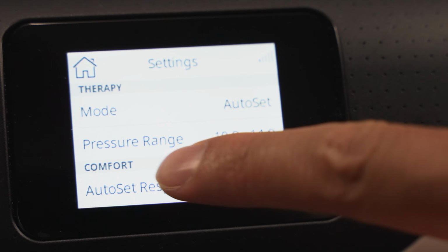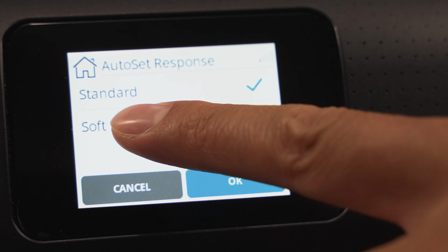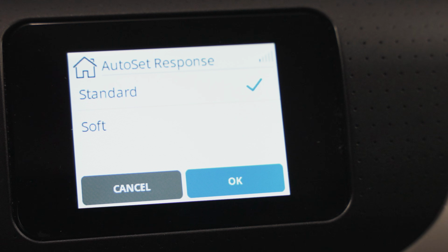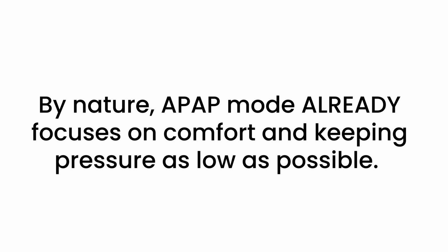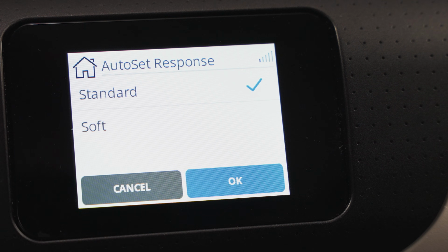Now let's go into comfort. So you're gonna see AutoSet response. That is soft or standard. Soft is a little more gentle of an algorithm. Now I always say that because an AutoSet algorithm or an APAP algorithm is always responsive, meaning that you have to have an apnea first before it starts ramping up that pressure. I like to keep it at standard because I think it's a little more responsive versus soft mode, which might be a little more gentle and a little more comfortable, but at the same time, it might not be ramping up as quickly as you need it.